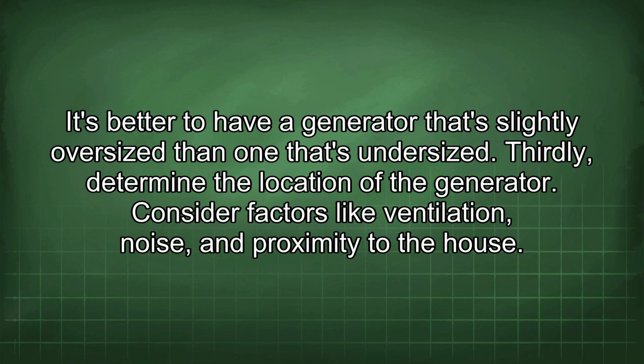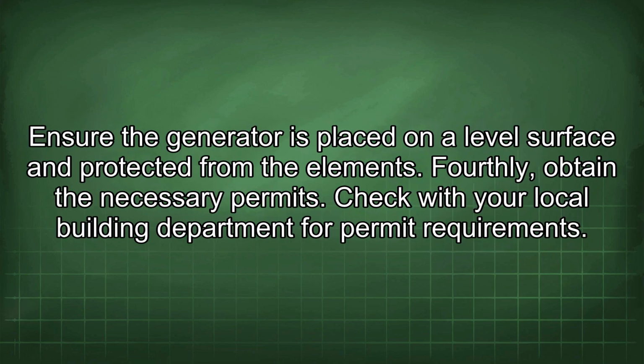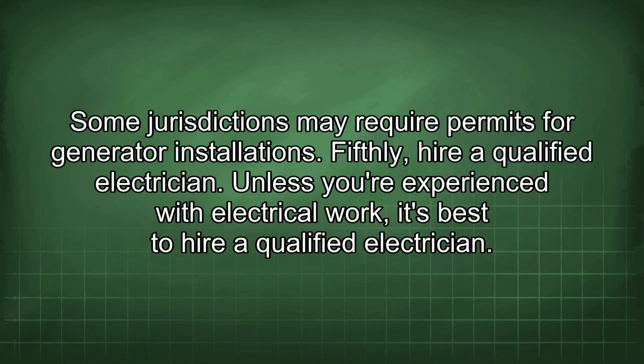Thirdly, determine the location of the generator. Consider factors like ventilation, noise, and proximity to the house. Ensure the generator is placed on a level surface and protected from the elements. Fourthly, obtain the necessary permits. Check with your local building department for permit requirements. Some jurisdictions may require permits for generator installations. Fifthly, hire a qualified electrician.